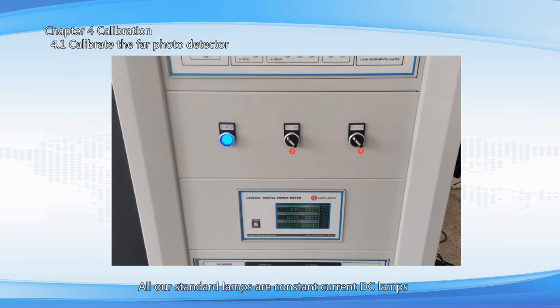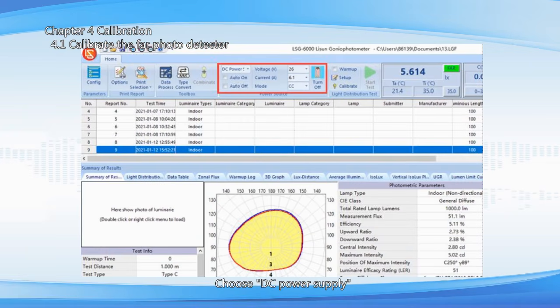All our standard lamps are constant current DC lamps. Turn this switch to DC. The other switch can always be at the outside position and there is no need to change it. Choose DC power supply. Input the reference voltage and the rated current according to the certification. Choose CC mode. And click to turn on the standard lamp. The standard lamp needs about 15 minutes to get stable. Then we calibrate the system.